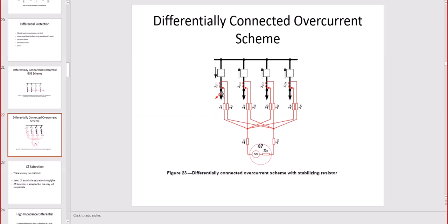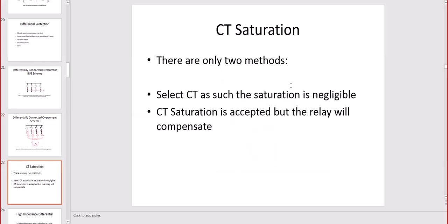And yes, the CT may be saturating, so we'll need to consider that. That's why, against the saturation, we have those impedances that limit the reading of the current in the relay, which protects the relay as well. So CT saturation is unavoidable unless you are using the new Hall effect current transformers that are based on the magnetic field, where you measure the magnetic field and amplify it into current. That is a different story, but it needs plus minus 12 volts.